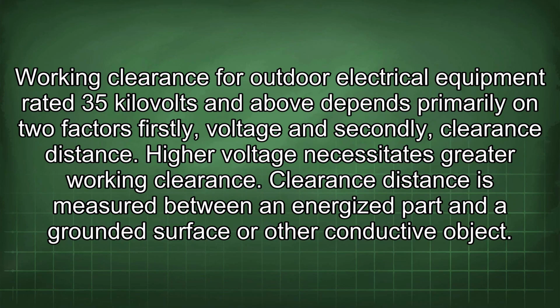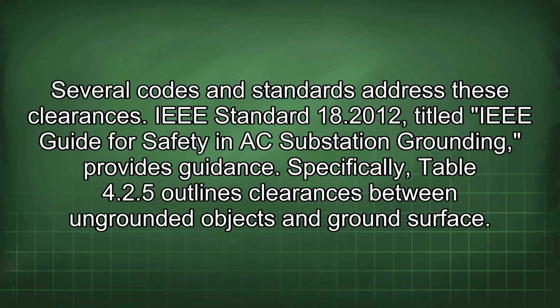Working clearance for outdoor electrical equipment rated 35 kilovolts and above depends primarily on two factors: firstly, voltage, and secondly, clearance distance. Higher voltage necessitates greater working clearance. Clearance distance is measured between an energized part and a grounded surface or other conductive object. Several codes and standards address these clearances.